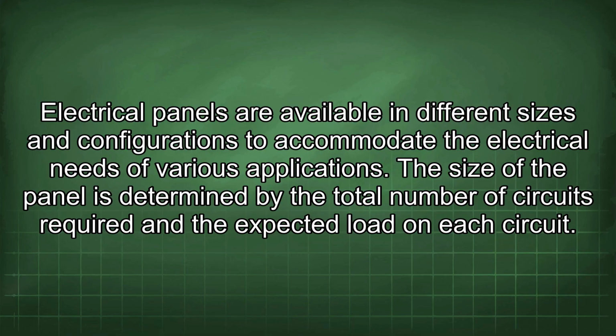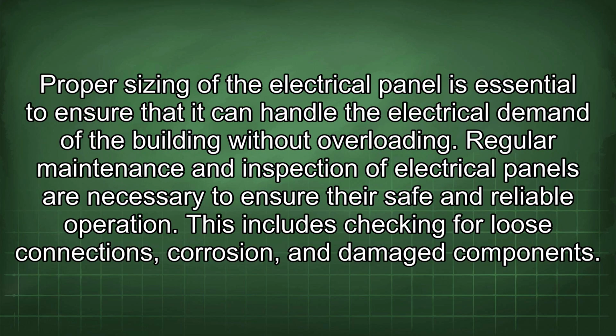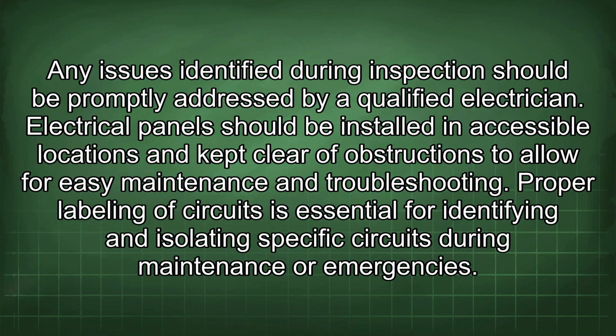The size of the panel is determined by the total number of circuits required and the expected load on each circuit. Proper sizing of the electrical panel is essential to ensure that it can handle the electrical demand of the building without overloading. Regular maintenance and inspection of electrical panels are necessary to ensure their safe and reliable operation. This includes checking for loose connections, corrosion, and damaged components. Any issues identified during inspection should be promptly addressed by a qualified electrician.